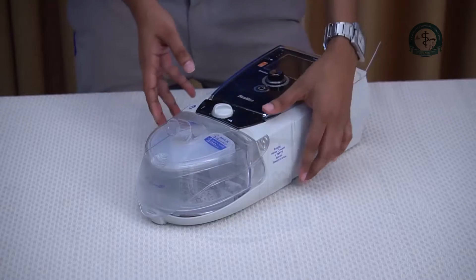Humidifier. This is a plastic part containing a container to store water. This lid can be opened and the water container can be taken out. We need to add sterile water to the container up to the level shown here. Once you fill up the container, place it back and close the lid. Then we can connect the humidifier to the main unit by pressing it in. Of course, we do not need to remove the humidifier to fill up the water container.